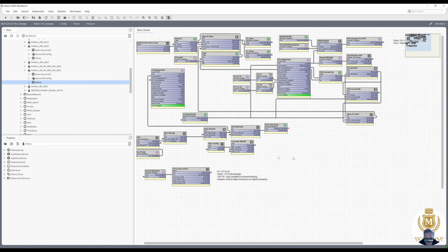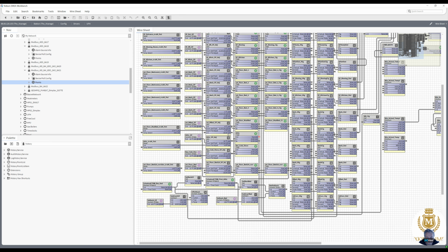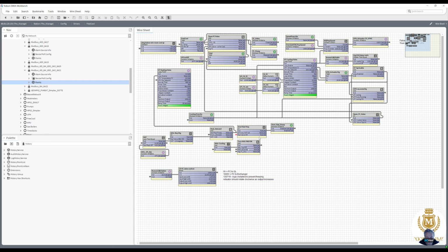Okay. So as you enable there, is that saying rad valve on? When we know the rad valve is now off, where is it getting that from? Again, from the same point. Okay. All we need to do there is tie back in.